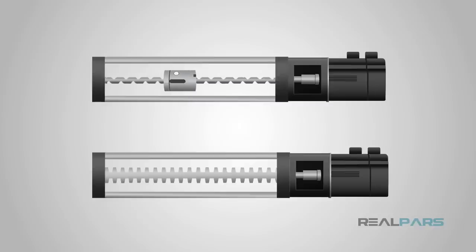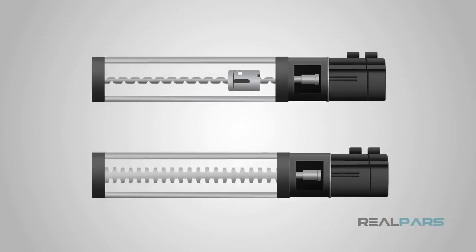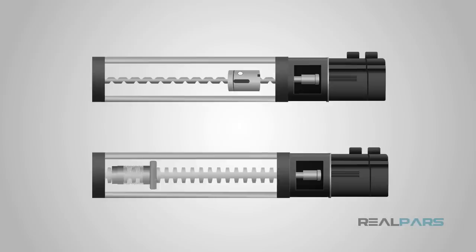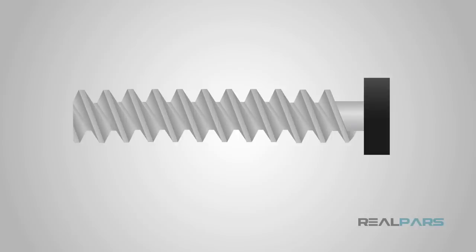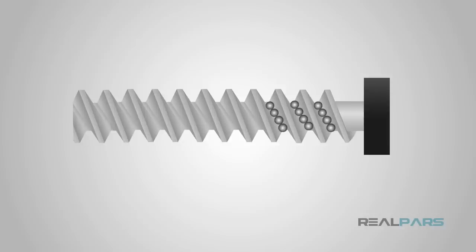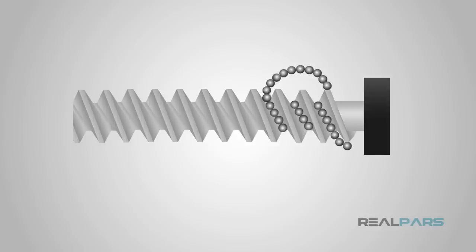Ball screw actuators use ball bearings and are more expensive, but provide less friction compared with lead screw actuators. In a ball screw drive, ball bearings travel along the grooves in a threaded shaft and the ball screw, and recirculate through a ball nut. Because bearings share the load, ball screw linear motion drives have relatively high thrust capacity. A ball screw drive combines repeatable motion and a stiff system that handles high forces and moments. Such systems work well in precision positioning applications with high loads and high duty cycles.